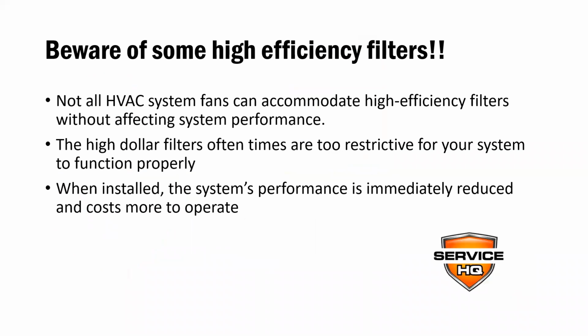Now, beware of some high efficiency filters, because not all HVAC system fans can accommodate high efficiency filters without affecting system performance. Those high dollar filters that you see, and I've seen them in all the different department stores, oftentimes they're too restrictive for your system to actually function properly. So as soon as you install that, the system's performance is immediately reduced and the cost goes up to operate your equipment. So they're not always a good thing.